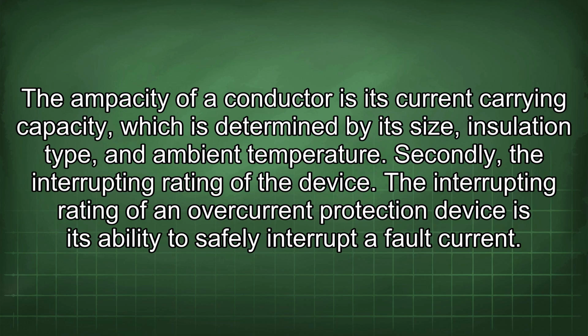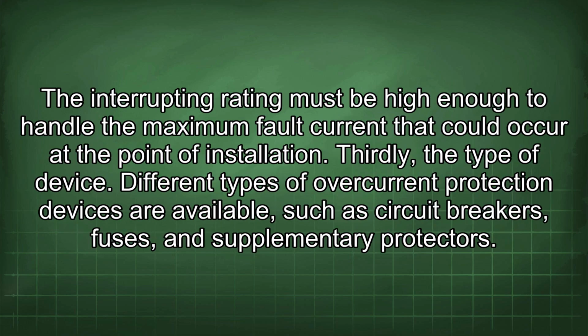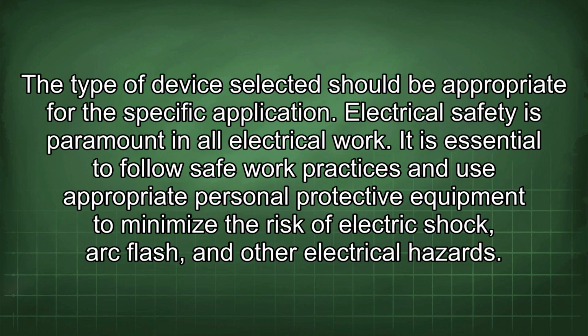The interrupting rating of an overcurrent protection device is its ability to safely interrupt a fault current. The interrupting rating must be high enough to handle the maximum fault current that could occur at the point of installation. Thirdly, the type of device. Different types of overcurrent protection devices are available, such as circuit breakers, fuses, and supplementary protectors. The type of device selected should be appropriate for the specific application.